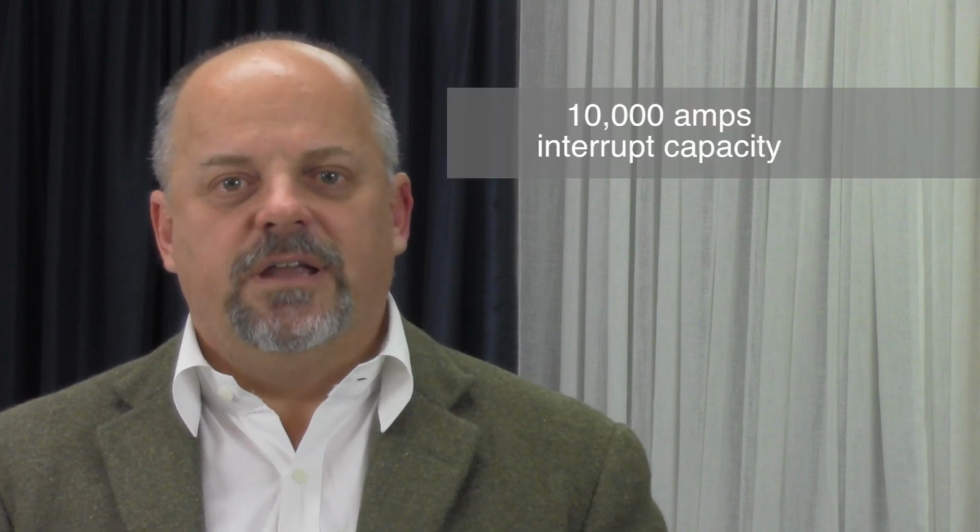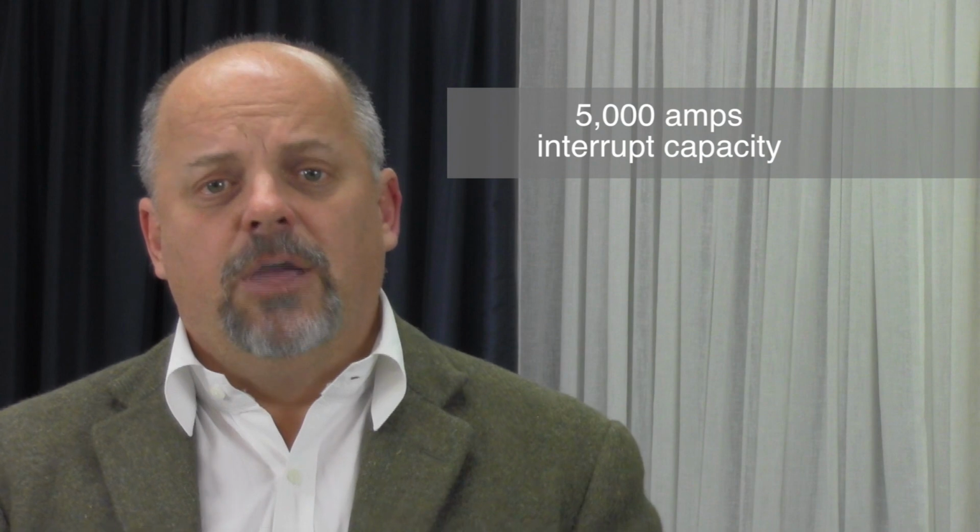Now also for your main power inlet overcurrent protection, that circuit breaker or fuse, you want to pick a large enough overcurrent protective device to work with your facilities where you send your product. So if you're sending an industrial product out for, say, semiconductor, you want to have at least 10,000 amps interrupt capacity. Now if you're using a cord and plugged in piece of equipment, you can drop that number to 5,000. But I still recommend using that UL branch breaker with 10,000 amps of interrupt capacity.